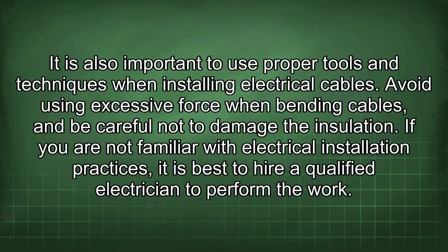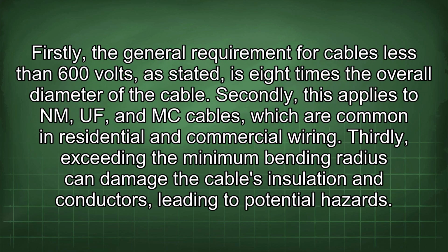It is also important to use proper tools and techniques when installing electrical cables. Avoid using excessive force when bending cables, and be careful not to damage the insulation. If you are not familiar with electrical installation practices, it is best to hire a qualified electrician to perform the work.